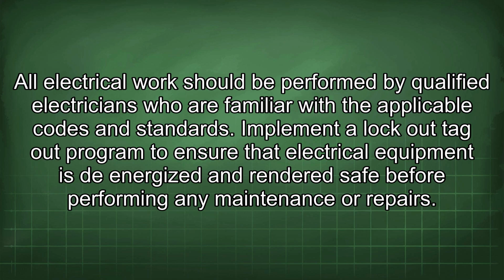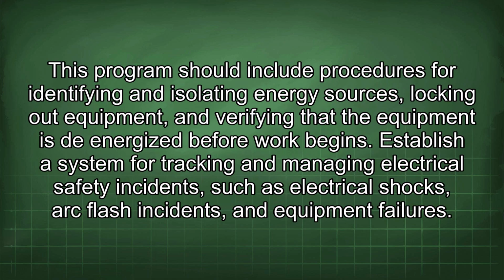Implement a lockout-tagout program to ensure that electrical equipment is de-energized and rendered safe before performing any maintenance or repairs. This program should include procedures for identifying and isolating energy sources, locking out equipment, and verifying that the equipment is de-energized before work begins.